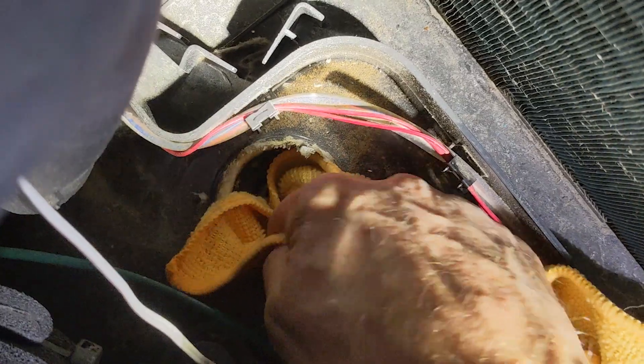There it is — the thing I should have replaced two years ago. I'm replacing it with a Corro-Protec. It's an electrified unit rather than using chemistry for the sacrificial anode.